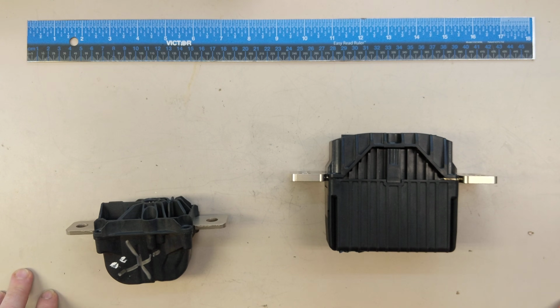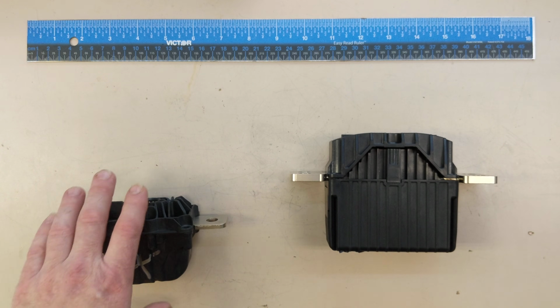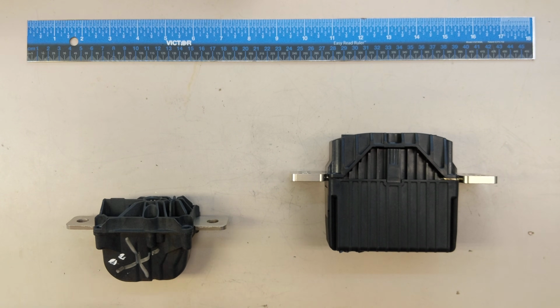As I went over in the other video, and I don't want to rehash too much, as performance improved in the cars, Tesla found they had a lot of nuisance trips. If you set the fuse low enough to protect the electronics, you end up with fuses that blow sometimes after repeated hard accelerations, because that's thermal cycling the fuse elements. So the Pyrofuse was - I wouldn't say invented - but they started using it because they can control it quite accurately.